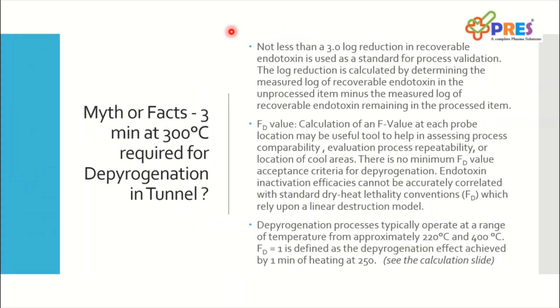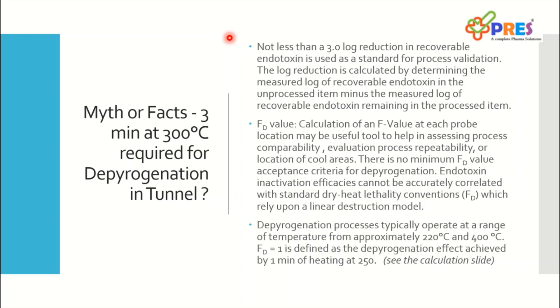Friends, not less than a 3-log reduction in recoverable endotoxin is used as a standard for process validation of a depyrogenation tunnel. The log reduction is calculated by determining the measured log of recoverable endotoxin in the unprocessed item minus the measured log of recoverable endotoxin remaining in the processed item, which is exposed to heat during the study. That's how you calculate how much log reduction you have achieved during the process.